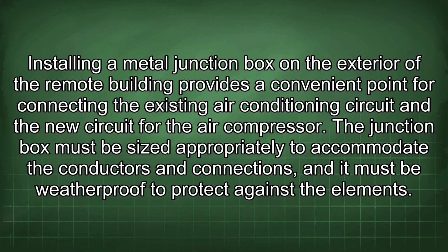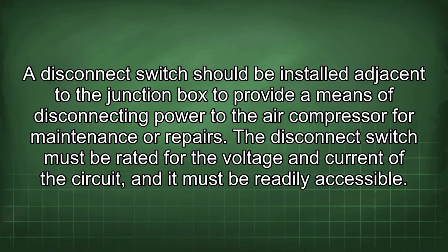Installing a metal junction box on the exterior of the remote building provides a convenient point for connecting the existing air conditioning circuit and the new circuit for the air compressor. The junction box must be sized appropriately to accommodate the conductors and connections, and it must be weatherproof to protect against the elements. A disconnect switch should be installed adjacent to the junction box to provide a means of disconnecting power to the air compressor for maintenance or repairs. The disconnect switch must be rated for the voltage and current of the circuit, and it must be readily accessible.